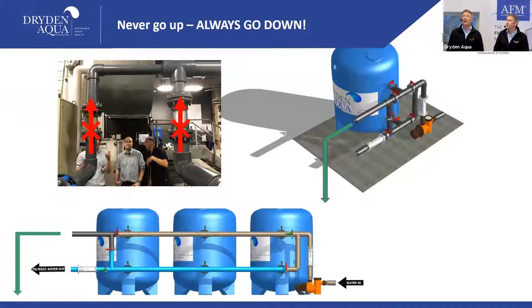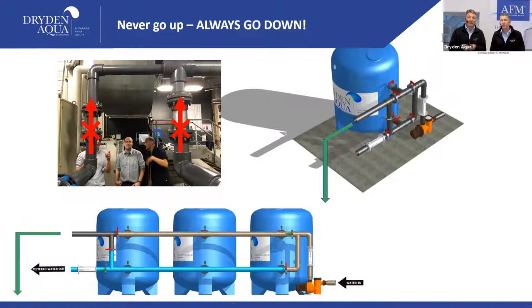A Belgian installation was very proud of their transparent backwash line going two meters upward — don't do this. A backwash line must be free-flowing, ideally pressure-free. Never route the backwash line upward; always route it downward.